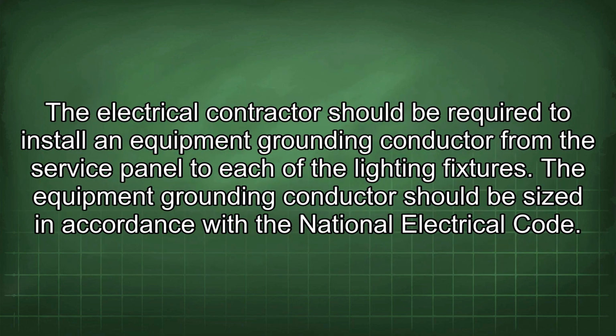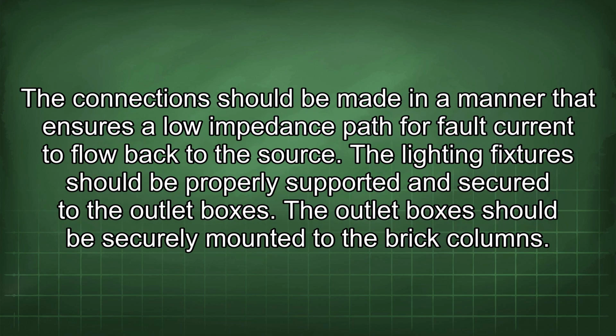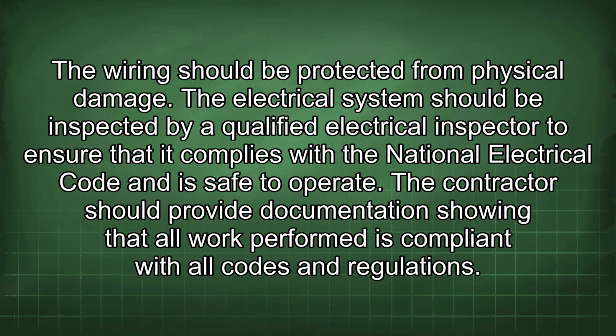The electrical contractor should be required to install an equipment grounding conductor from the service panel to each of the lighting fixtures. The equipment grounding conductor should be sized in accordance with the National Electrical Code. The connection should be made in a manner that ensures a low impedance path for fault current to flow back to the source. The lighting fixtures should be properly supported and secured to the outlet boxes. The outlet boxes should be securely mounted to the brick columns. The wiring should be protected from physical damage.